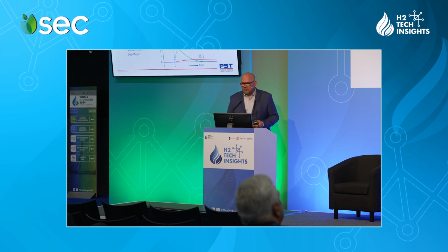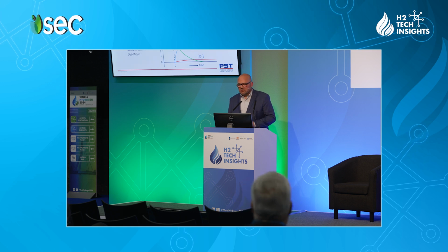In the first period, of course, there will be a constant flow of nitrogen. It's being purged. And then at the start, when the power is switched on, hydrogen starts to build up, oxygen starts to build up, and the nitrogen will be replaced according to that formula. The constant, again, depends on the size of your unit, how much dead space is there, how much hydrogen is being produced, which is, again, a function of the power, of course. But typically, a curve like this will exist.